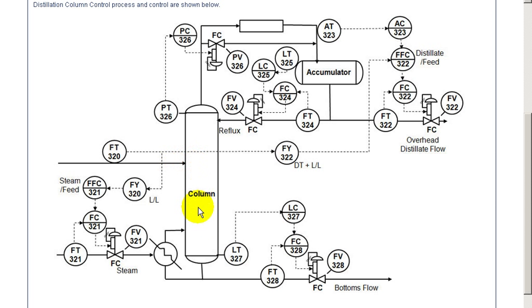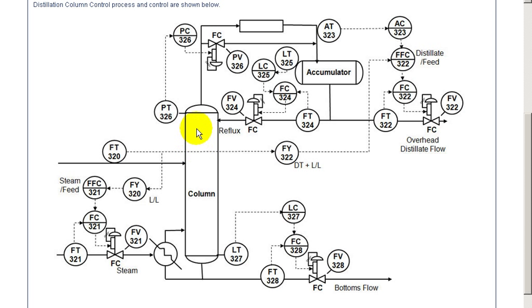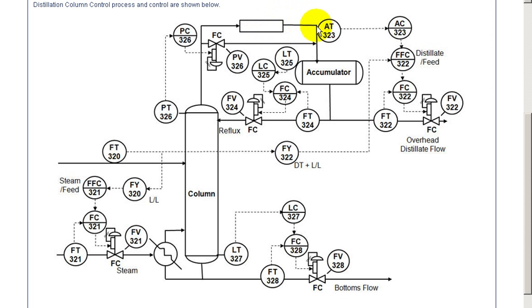The material entering falls to the bottom of the column where it is then heated through an external heater. The steam to the heater is adjusted to adjust the boil up. The vapor that comes up the column then goes through a heat exchanger where it condenses and falls into an accumulator as a liquid.